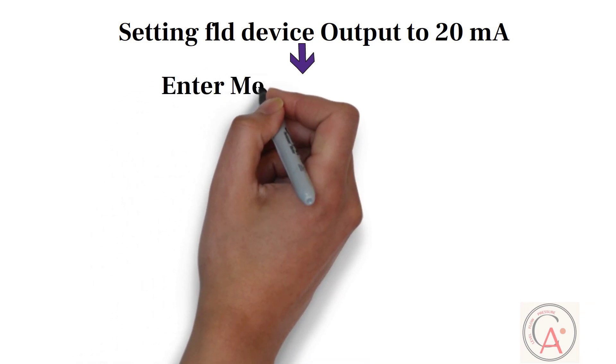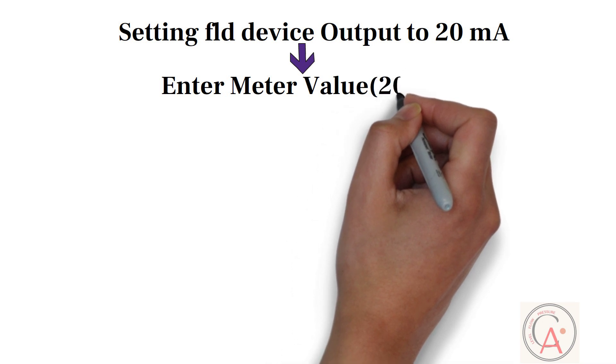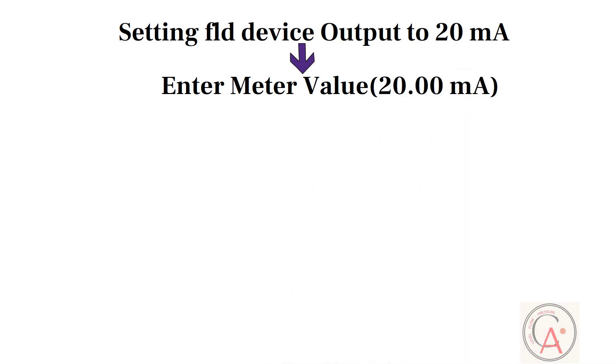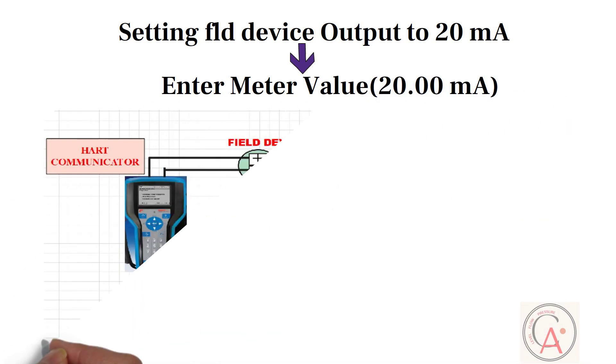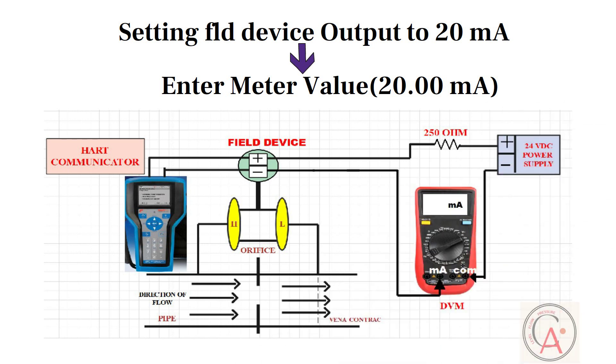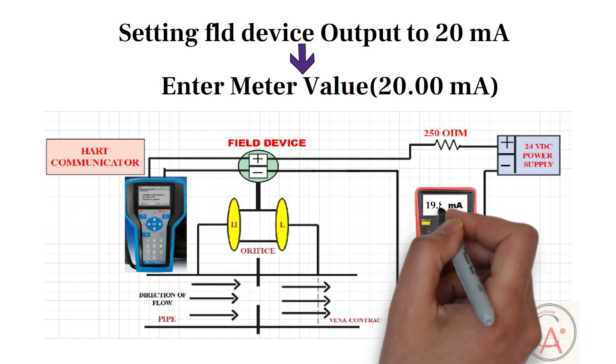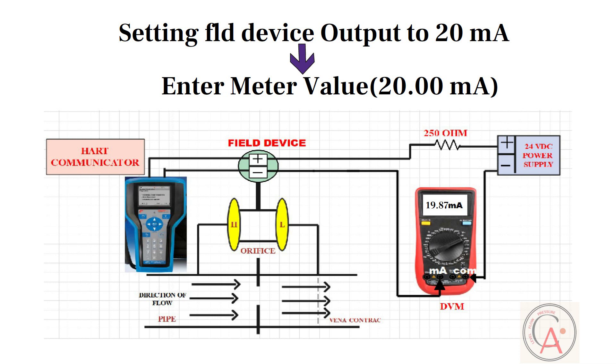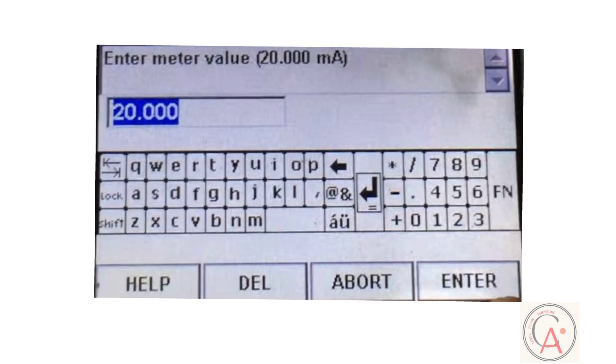After this, ENTER milliampere option will display on the screen. At this time, enter the milliampere value of ampere meter into HART communicator. For example, if ampere meter reads 19.87 milliampere, then enter 19.87 milliampere into HART communicator and press ENTER button.